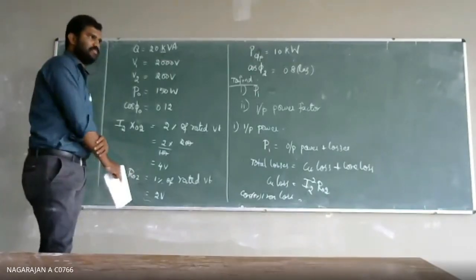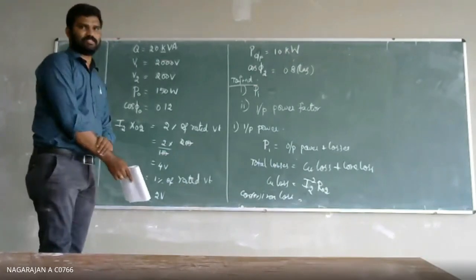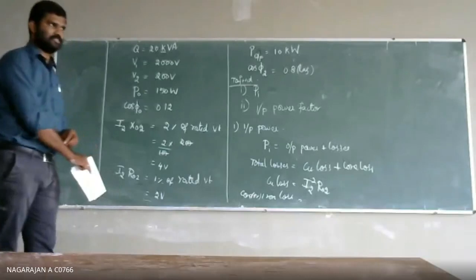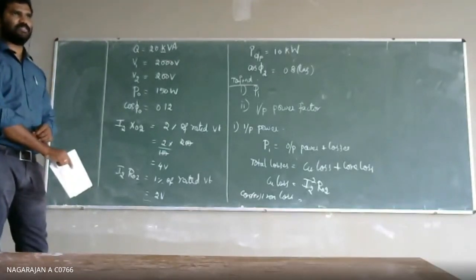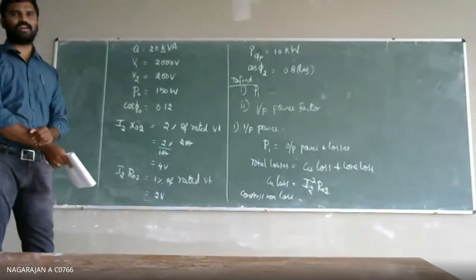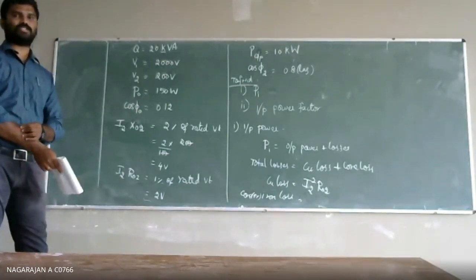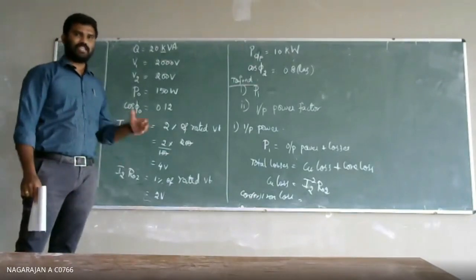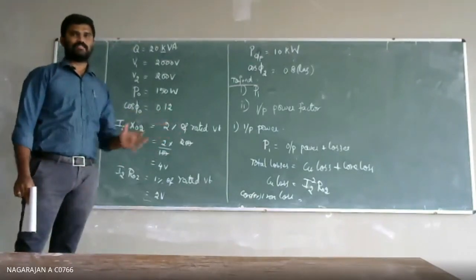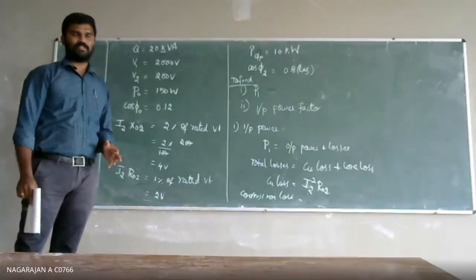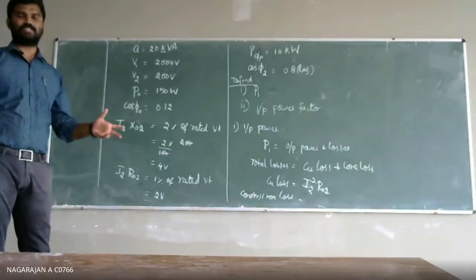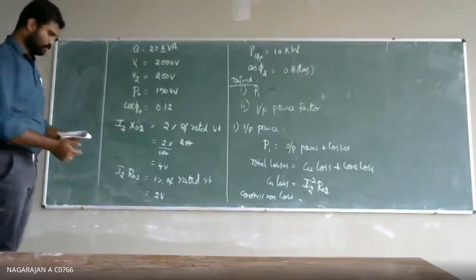Sir, Kerala, sir. In a transformer, how can you identify the total iron loss? Don't know, sir. Okay. Please go through no load and full load test, sorry, short circuit test of a transformer. At no load test, whatever we give as an input will be selected as iron loss. The result of no load test, the power value measured at no load test, is the iron loss.